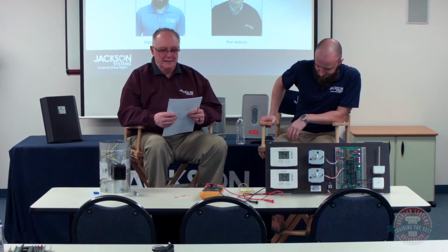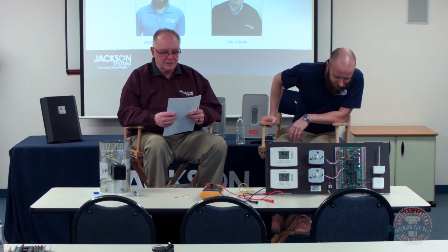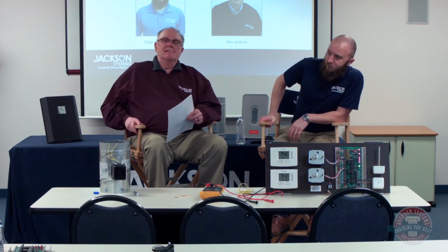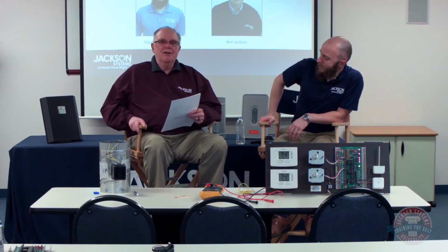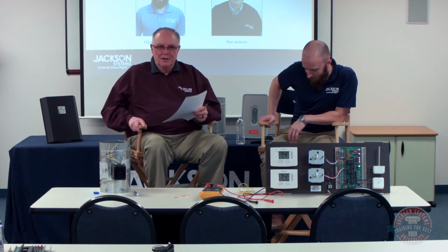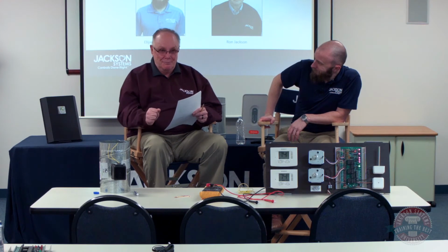He asked, if I zone the supply ducts and don't zone the returns, will I be depressurizing closed door rooms? I'm going to answer that a little bit different than the way the question was asked. I only know of one case where return air dampers were installed. That was in my home. And it really can make sense, but because of the expense, nobody wants to do it.